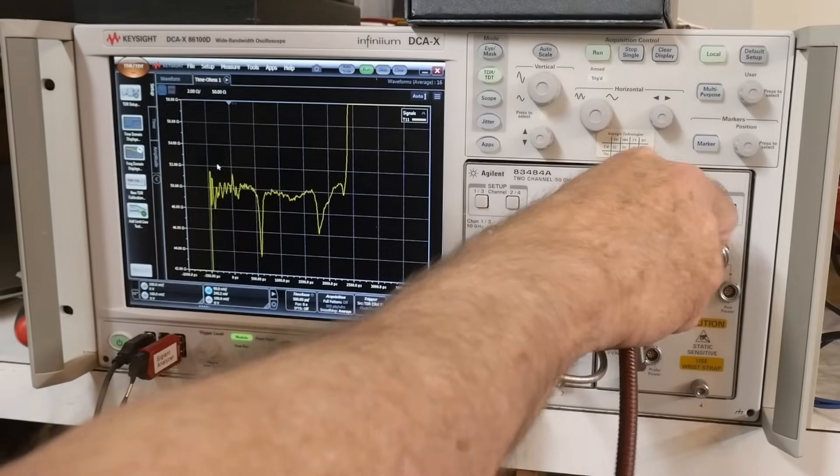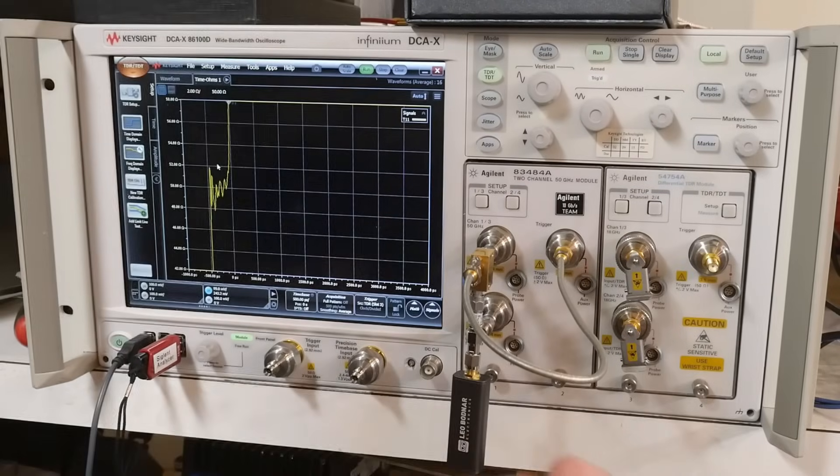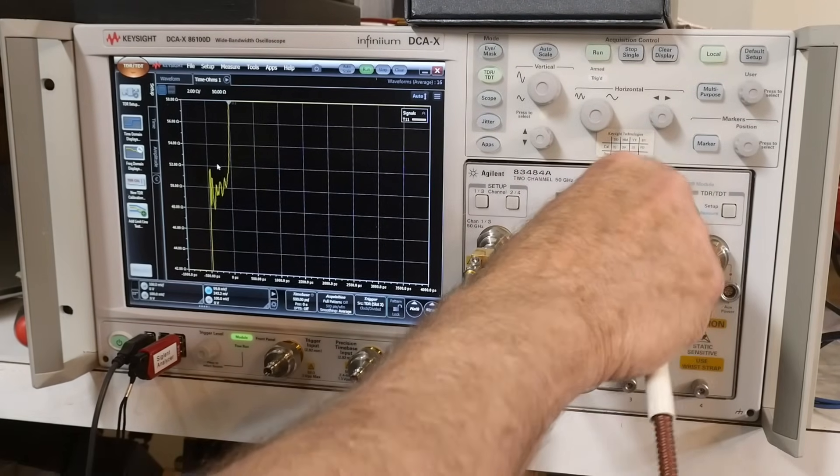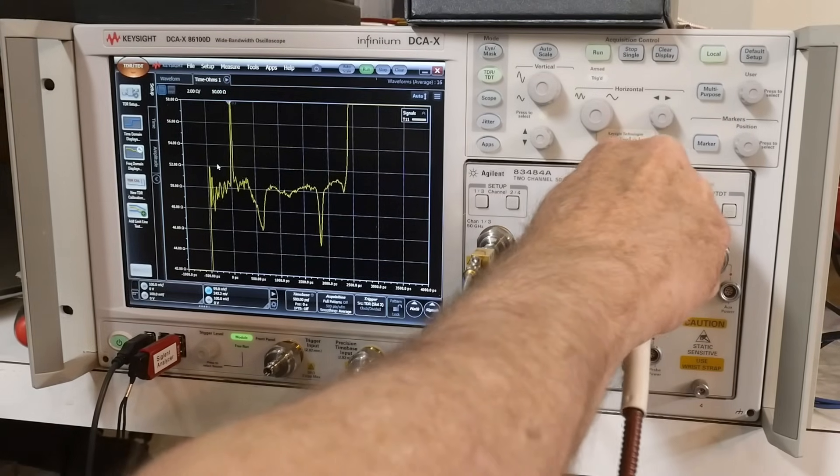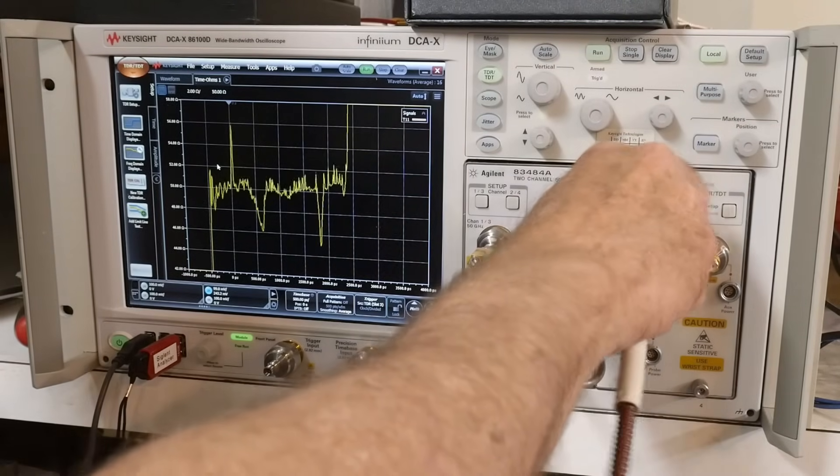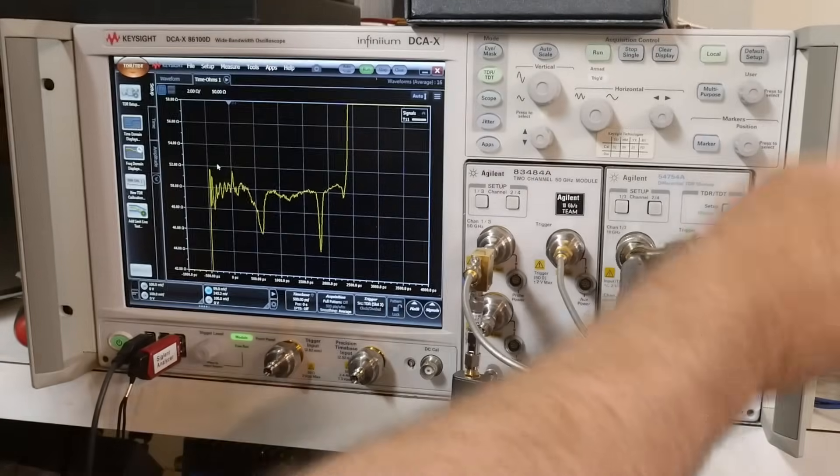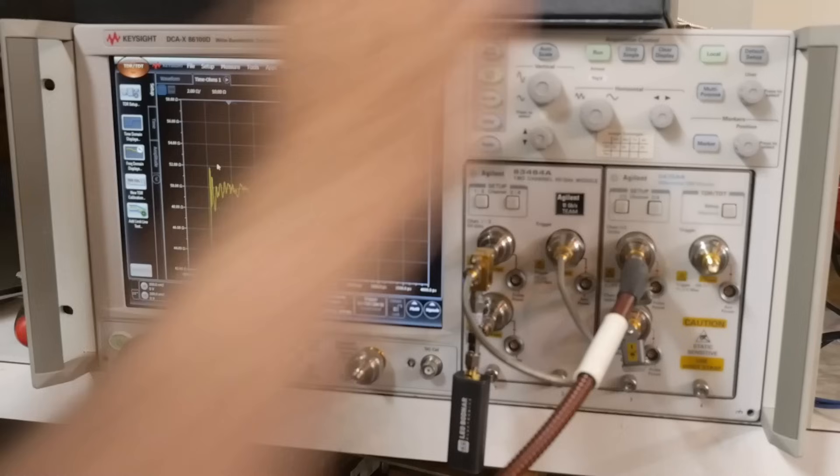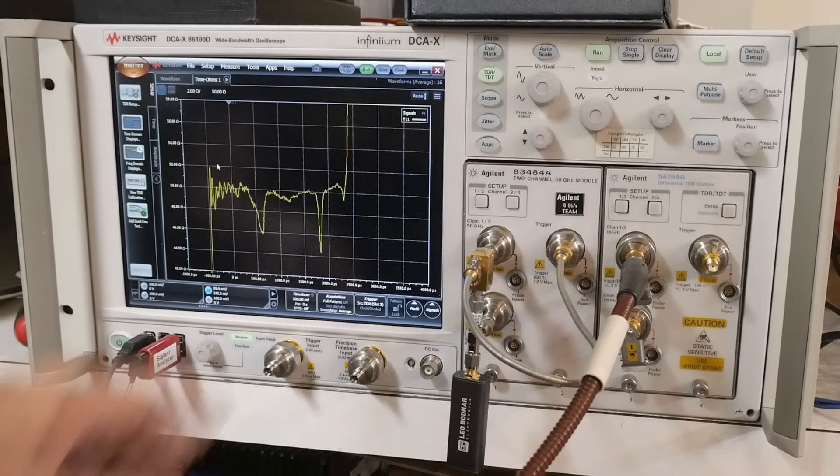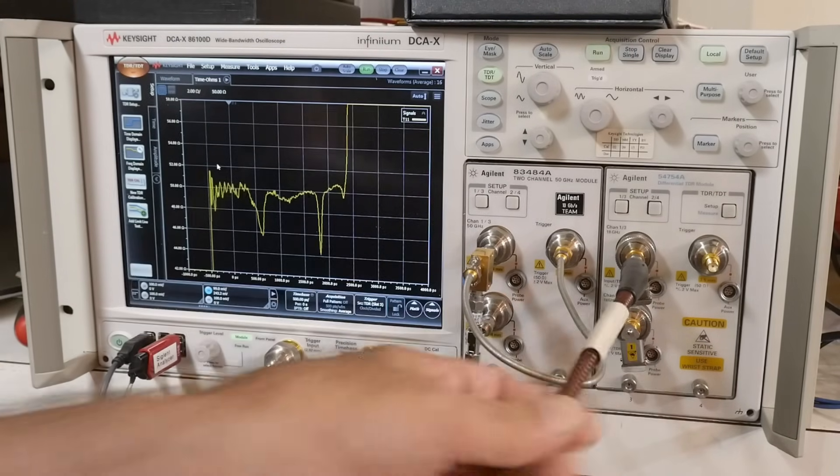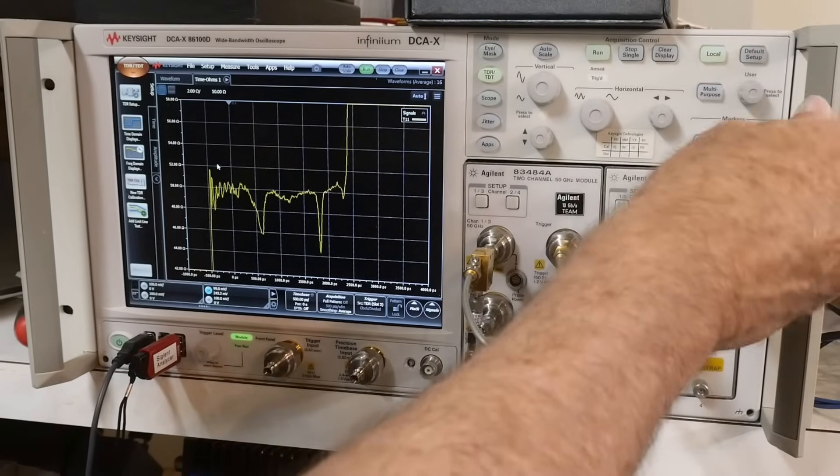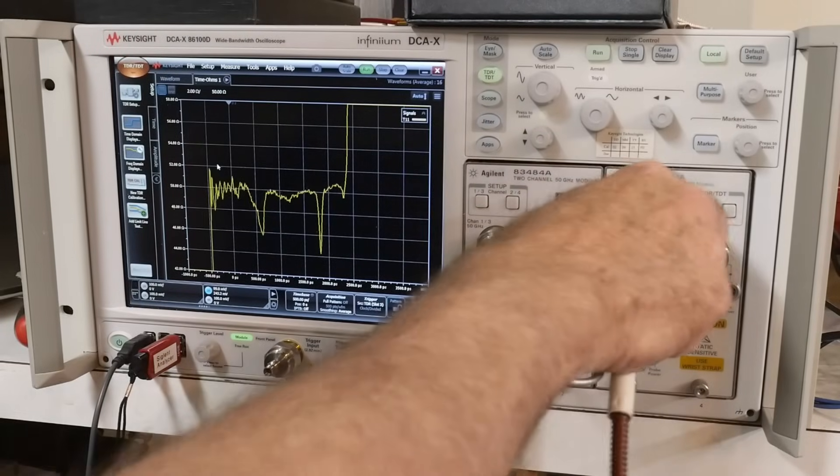It looks like, looks like the shielding has come loose. Like right at the beginning here. Wow. I'm really shocked about that one. That other Gore cable was absolutely perfect, but this one looks like crud. I got to test the cable. I use these cables on my big VNA. Now a lot of times you'll just calibrate this out and you won't be bothered by it too much. But it's certainly something you don't want in a metrology situation. Wow. Yeah. This one's got some real problems. I don't know if that's inherent to the way these cables are built or whatever. Wow. Okay. Learned something new. That other Gore cable was like superstar. That's what I would expect from a Gore cable. He's absolutely perfect in every way. Practically perfect in every way.